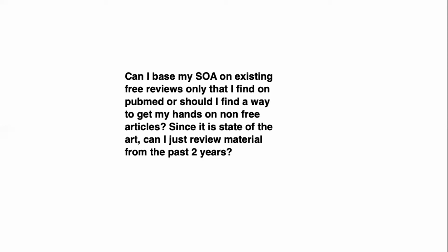All right. So again, the state-of-the-art depends on the searches that you do for it. I would not recommend internet searches only, which I think is at the heart of this question, finding things on PubMed or for free. The notified bodies are looking very, very carefully at literature search methodology, most certainly for your own device under evaluation, but also for your state-of-the-art.